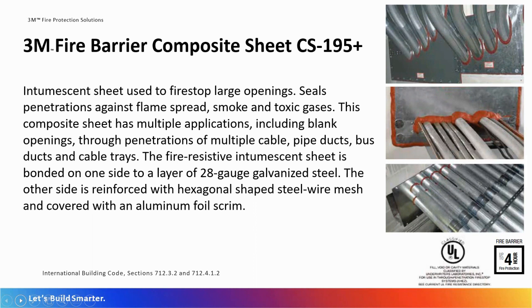Again, it's an intumescent material. It's great to use for blank openings in fire-rated walls or where you have multiple penetrating items like cable, conduit, bus duct. Any voids or openings in this material will typically get filled with either our putty or our CP25WB plus sealant. And in fact, the pictures you see there around the penetrating items and around the perimeter of the composite sheet, it's all sealed with CP25WB plus sealant. Next slide, please.